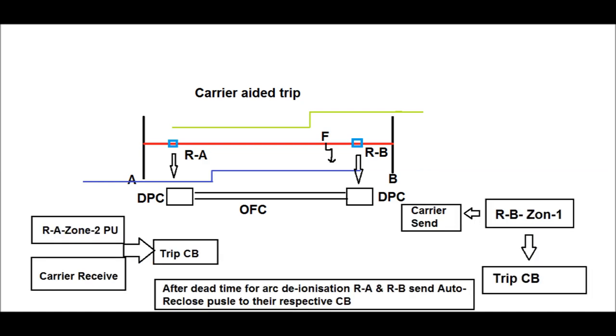In this diagram, the logic has been shown for the carrier aided protection scheme as well as the autoreclose for both circuit breakers. Since the fault occurs at a point which lies in zone 1 for relay B and zone 2 for relay A, the zone 1 relay at the B end sends a carrier send as well as trips the B end circuit breaker instantaneously. The carrier is sent through the DPC, or digital protection coupler, which converts the analog channel to the digital channel and transmits it by optical fiber cable, and it is received at the far end by a digital protection coupler. It converts the digital channel to analog and sends it to the relay end.